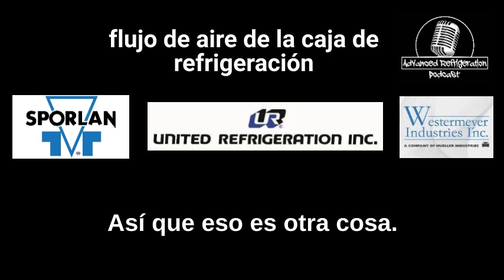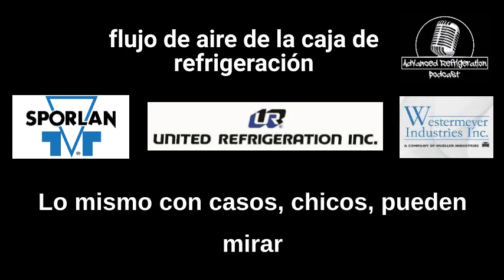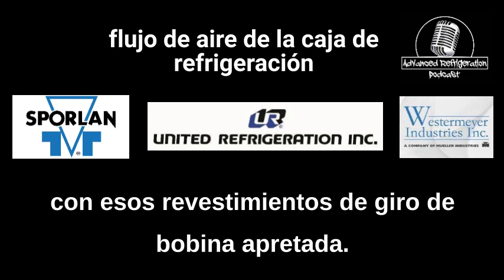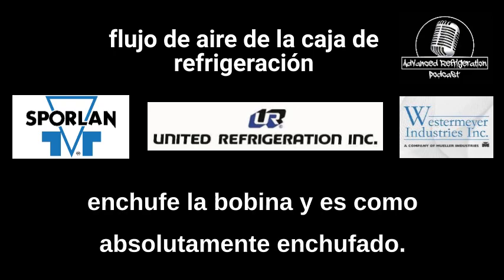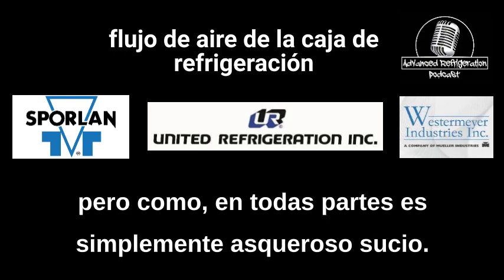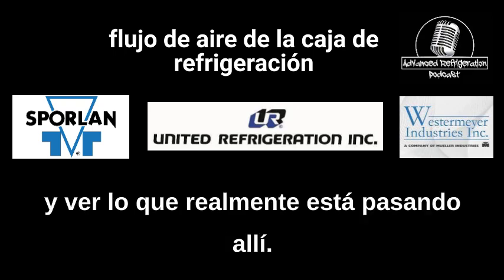I mean, so that's another thing, just actually get in there and look at the evaporators. Same thing with cases, guys. They can look clean behind those fans, but behind the shroud, where you can't see, especially Hill Phoenix cases with those tight coil fin spacings and the NRG cases. I don't know how many times I've seen guys miss a plugged coil, and it's absolutely plugged, but behind the fans it's got a little more static pressure, so it's pushing that dirt farther into the coil, and it looks somewhat clean behind the fans, but everywhere else is just filthy dirty. So that's another thing. You flip that plenum over and see what's actually going on there.